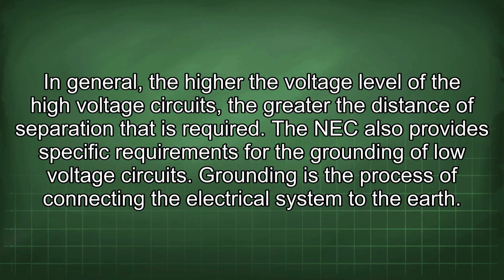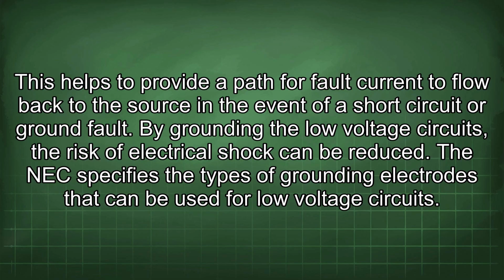The NEC also provides specific requirements for the grounding of low-voltage circuits. Grounding is the process of connecting the electrical system to the earth. This helps to provide a path for fault current to flow back to the source in the event of a short circuit or ground fault. By grounding the low-voltage circuits, the risk of electrical shock can be reduced.